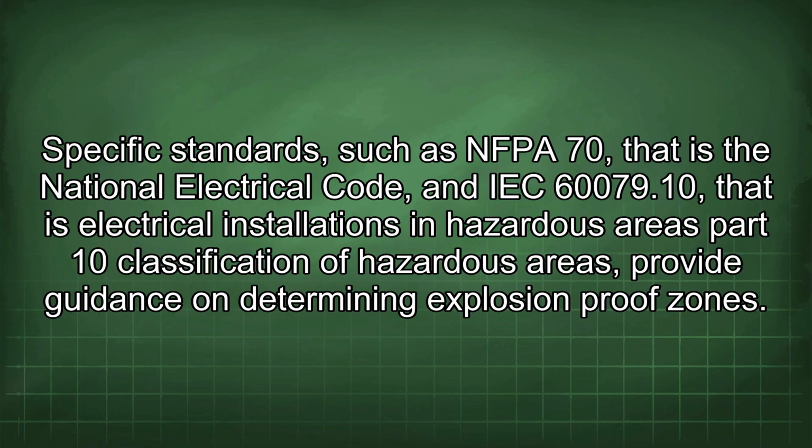Specific standards such as NFPA 70, that is the National Electrical Code, and IEC 60079-10, that is Electrical Installations in Hazardous Areas Part 10 Classification of Hazardous Areas, provide guidance on determining explosion-proof zones.